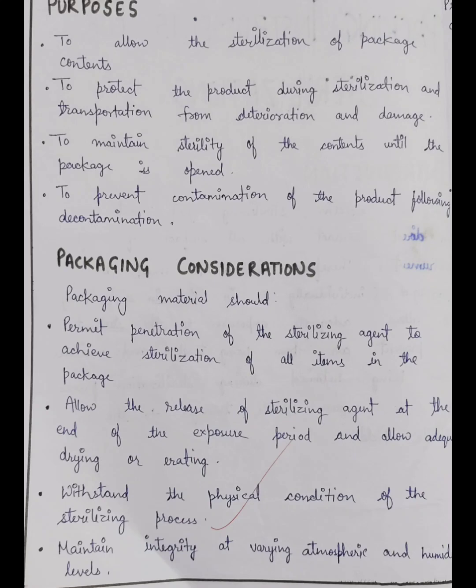Now let's look at packaging considerations. Packaging material should permit penetration of the sterilizing agent to achieve sterilization of all items in the package. Poor quality material should not be used. Next, it should allow the release of the sterilizing agent at the end of the exposure period and allow adequate drying. It must also withstand the physical conditions of the sterilizing process.